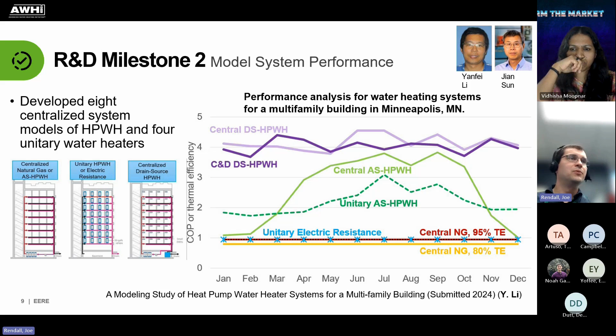It's pretty simple to model efficiency for central natural gas at 80 or 95%, and unitary electric resistance water heaters, since they're not very climate dependent. But in cold months in Minneapolis, central air source heat pump water heaters and even unitary ones aren't getting a very high COP. Whereas with a constant drain temperature year-round, maybe 65 Fahrenheit, you can still get a high COP, which is much easier than pulling heat out of air that's below or near freezing. Yanfei is going to be publishing a paper on this soon, it's almost out the door.